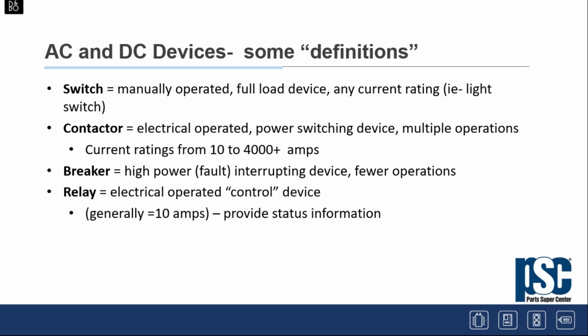A contactor, however, is an electrically operated power switching device designed for multiple operations. So you can have current ratings from anywhere from 10 amps to above 4,000 amps. But a contactor, again, is multiple operations, where the breaker, the next item down, is generally considered to be a high power or a fault interrupting device with relatively few operations. Now, there are some that are used multiple times a day, but breakers are generally considered to be fault interruption or high power interruption devices. And then a relay is basically an electrically operated control device, generally with a current rating of about 10 amps. And its function is to provide status information to either some other device or something in the control circuit. So just high level, some general definitions.